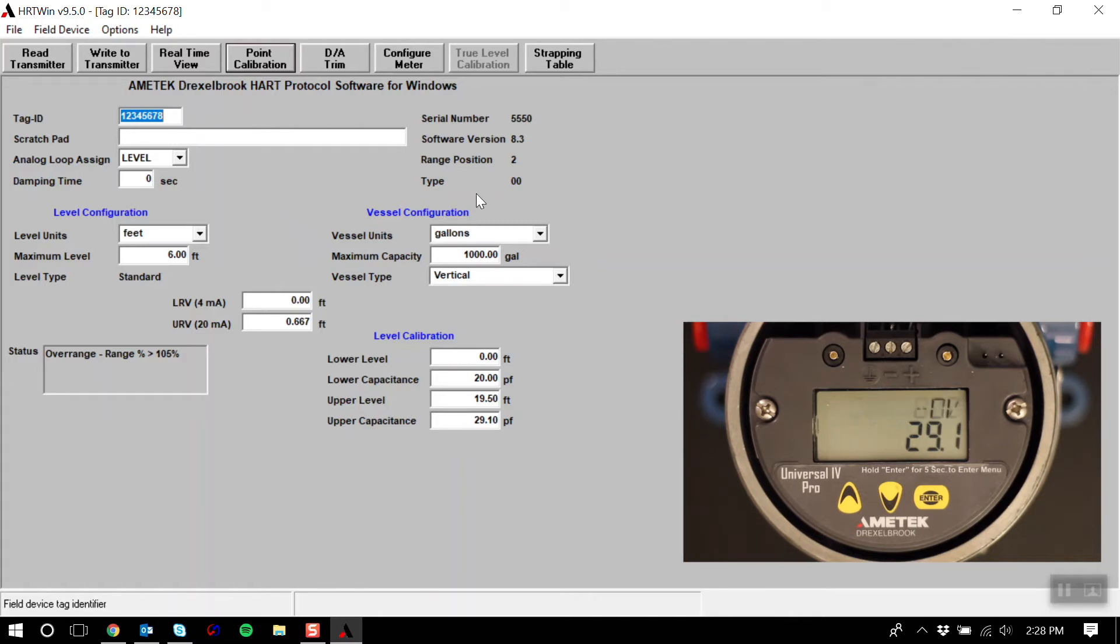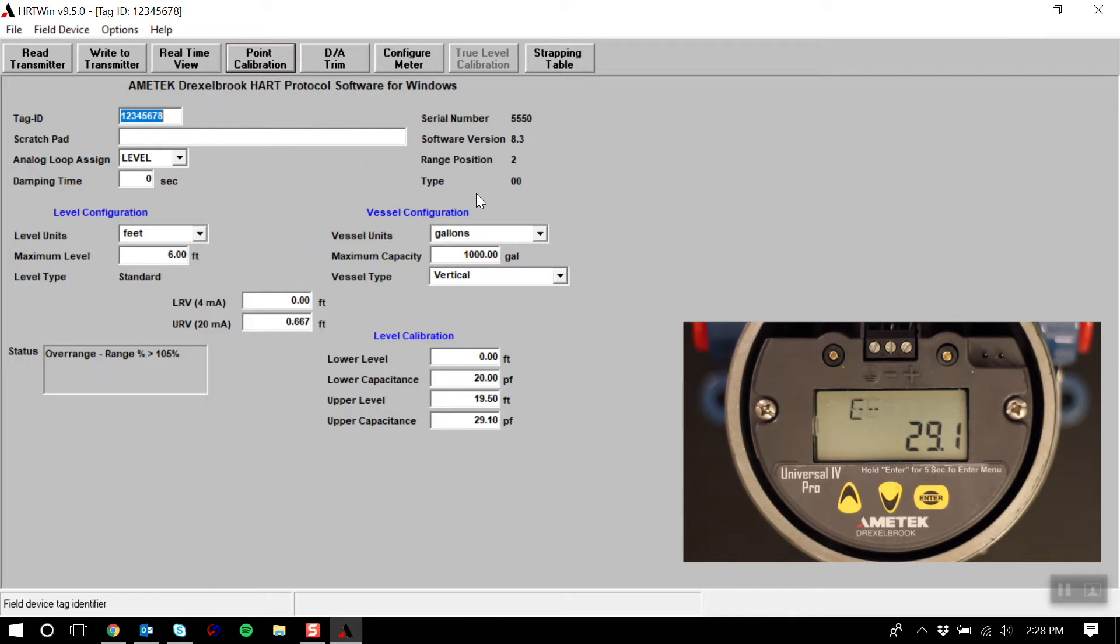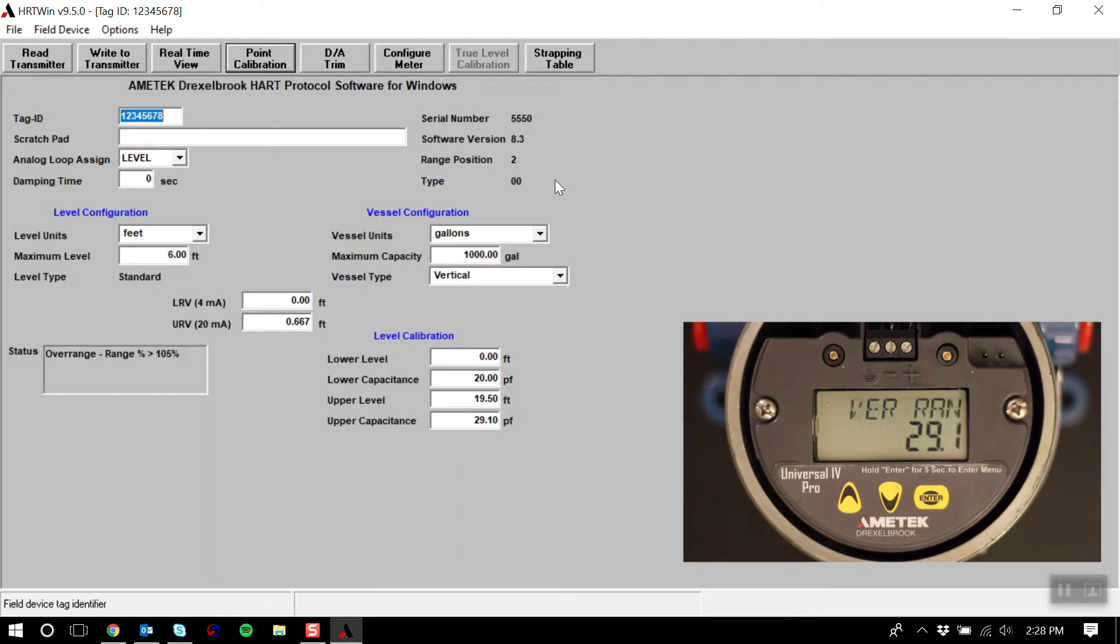The next option is calibration using capacitance values. This is used when you know the capacitance values in relation to your level values. For example, 16 feet equals 4800 pF. Just like the point calibration, you will need to know two points to create a linear output. The points do not have to be the lowest or the highest points in your measurement.